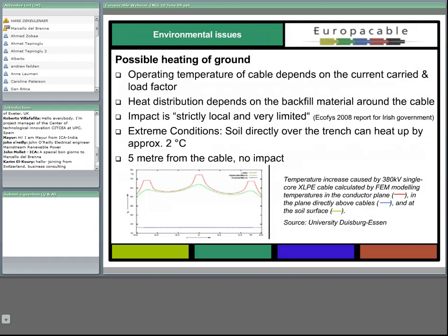The graph which has been developed by the University of Duisburg-Essen with experience with XLPE cables and with finite elements modeling, shows what are the temperatures around the cable, and basically there is no effect as soon as you are 4 to 5 meters outside the corridor occupied by the cables.